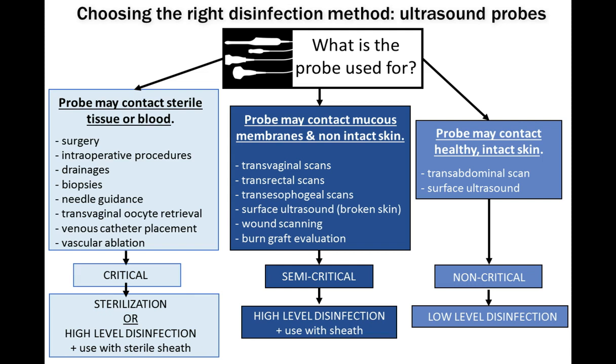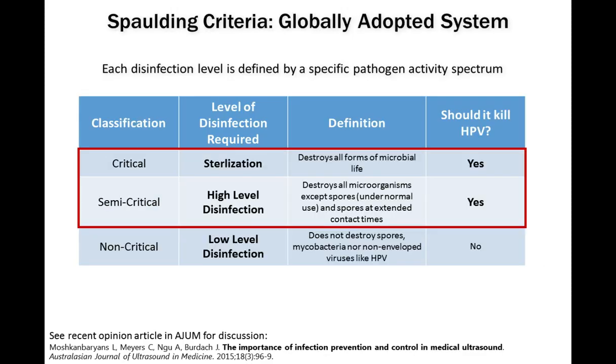If the probe contacts mucous membranes or non-intact skin, such as in transvaginal scans, transrectal and transesophageal scans, or other things listed in this box, then it is a classification of semi-critical, and it requires high-level disinfection with the use of a sheath. If the probe only contacts healthy or intact skin, such as in a transabdominal scan or a surface ultrasound, this is classified as non-critical and requires only low-level disinfection.